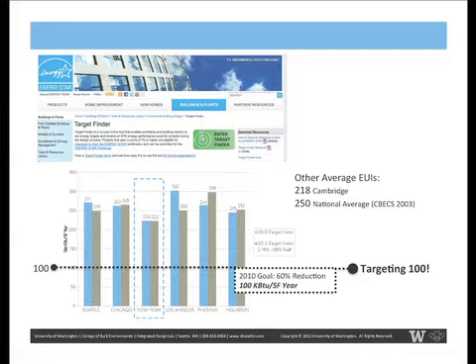And it really doesn't vary by climate, because these are such internally load dominated buildings. Our problem is to see if we can offload, take out some of that internal load, and then start to make them more climate specific. When we can pull out that load, which we'll show you how to do, all of a sudden the building in Phoenix looks a little different than the building in Seattle versus the building in Boston or New York.